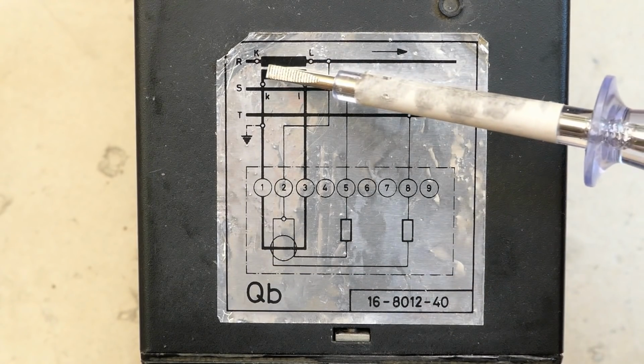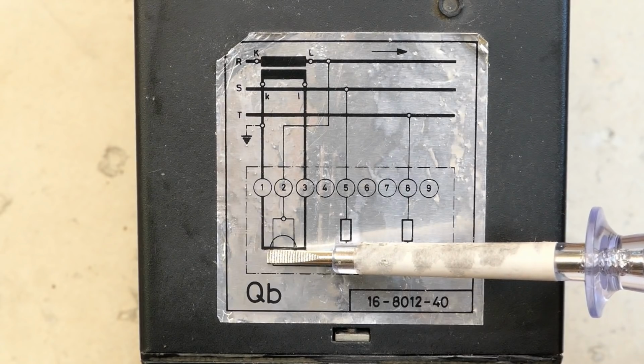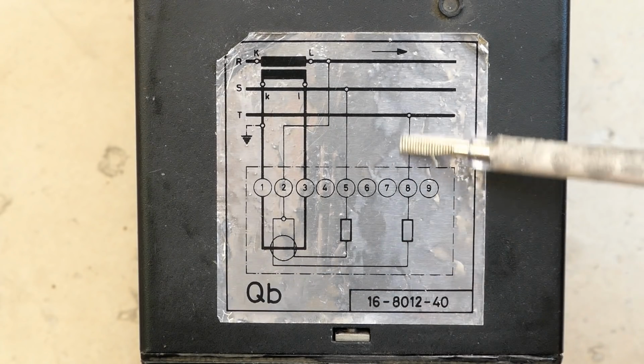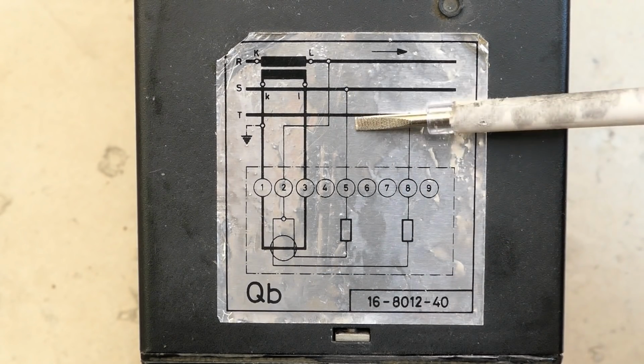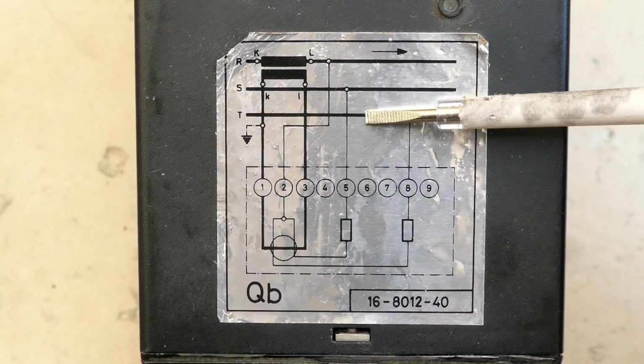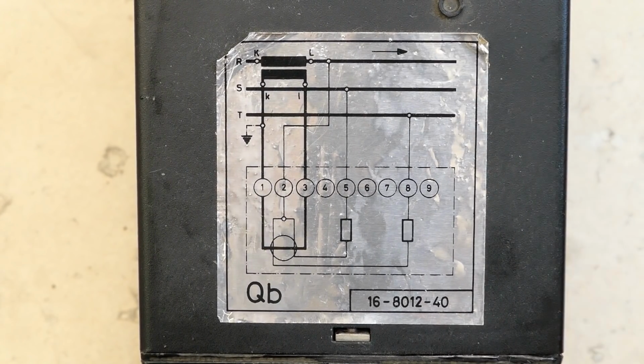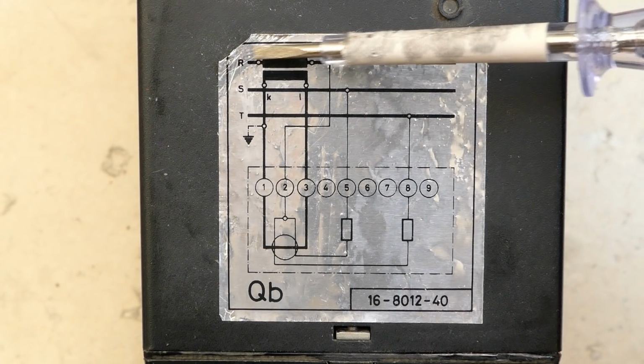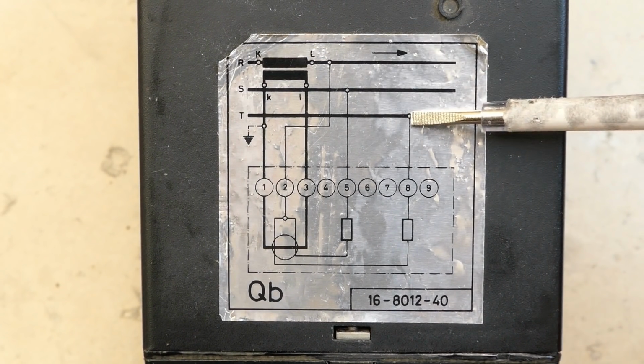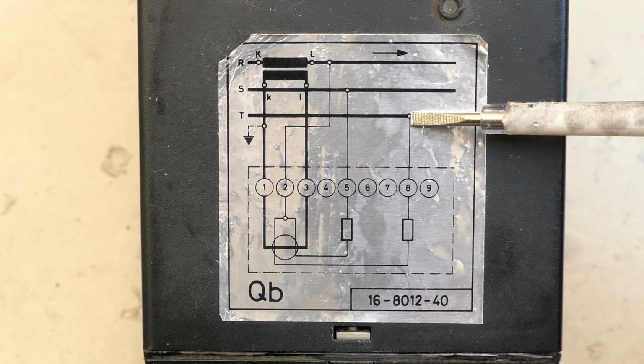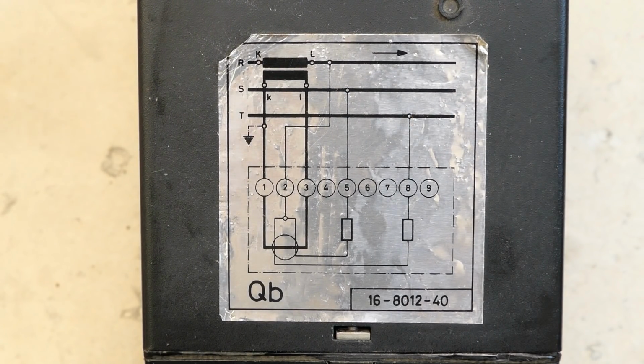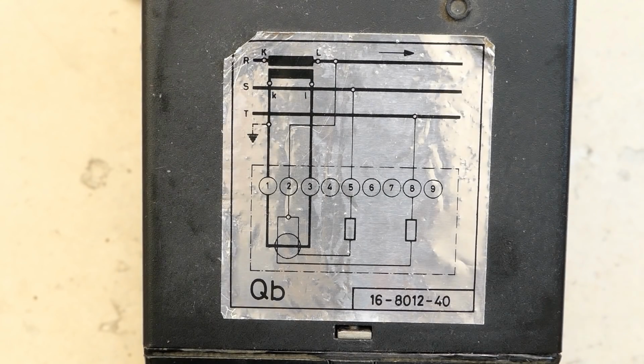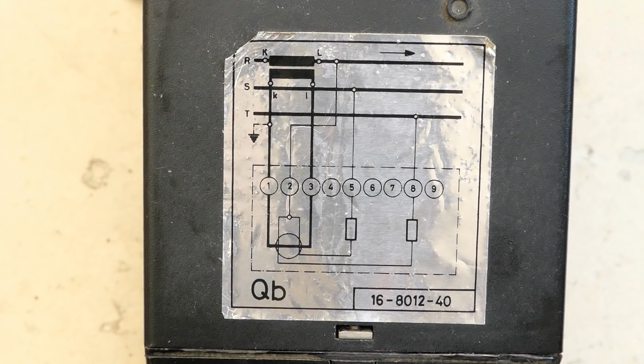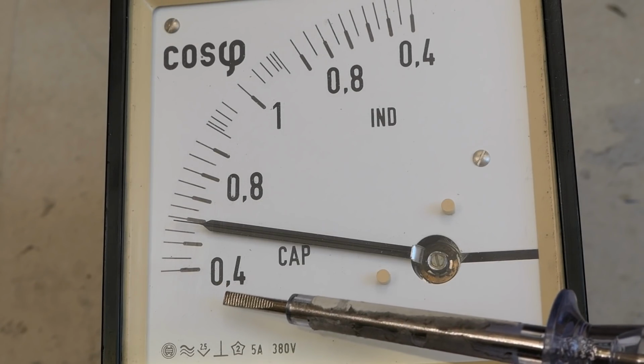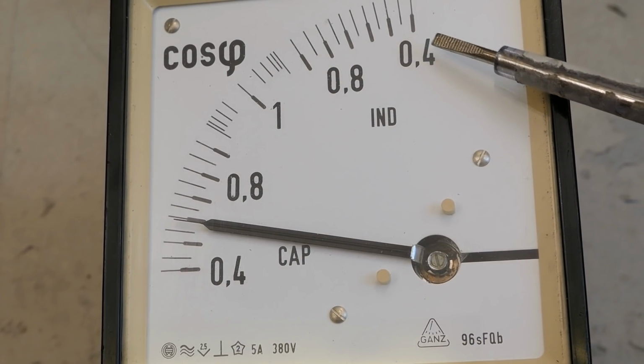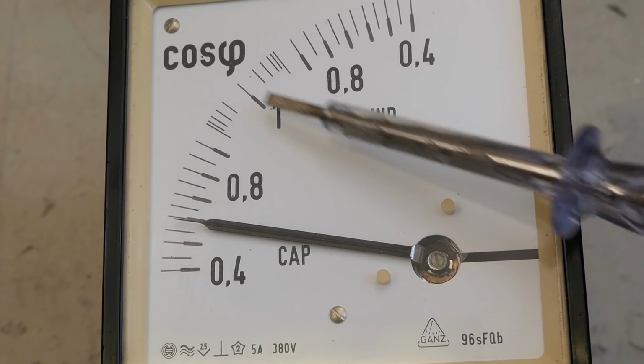And the phase of the current in the current sensing circuit is compared with the phase of these 2 phases, and one of these reference phases is ahead of this phase and one of them is behind this phase. This thing is basically sensing current in one phase but using the other 2 phases to generate a phase shift simply without having to use capacitors and inductors. But I guess it could be modified for a single phase operation. And this one measures from 0.4 capacitive all the way to 0.4 inductive with 1 in the middle.